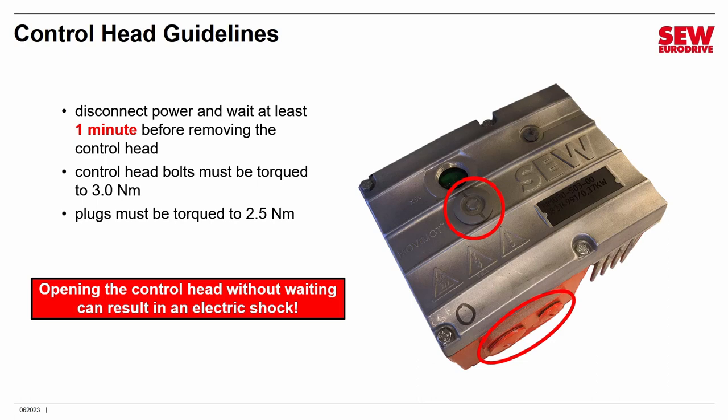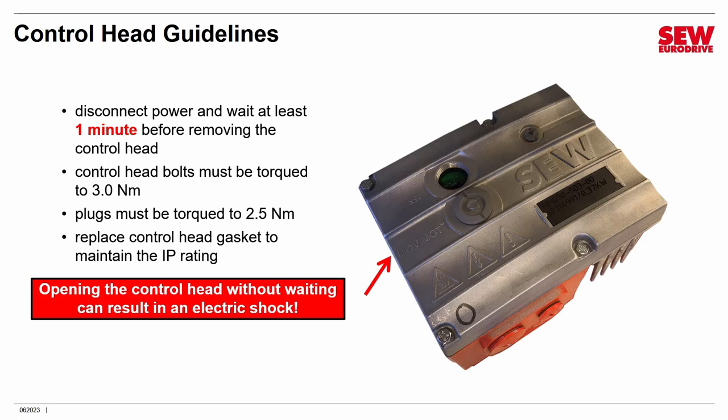Torquing the plugs to 2.5 newton meters is essential to maintain the IP rating. Also, the gasket between the control head and the conduit box should be replaced after you've opened it, especially if the MOVIMOT has been closed up for a long time. The gasket can develop a memory, and when you bolt the control head back down, it may not seal properly. A new gasket eliminates this problem and is a very inexpensive way of ensuring the MOVIMOT stays sealed in dirty or wet environments.